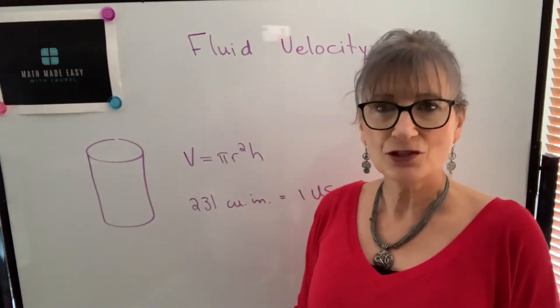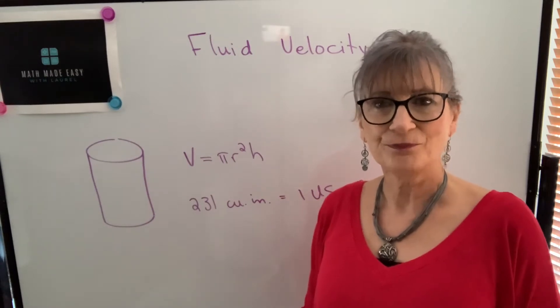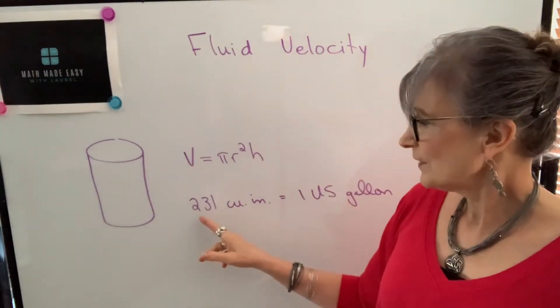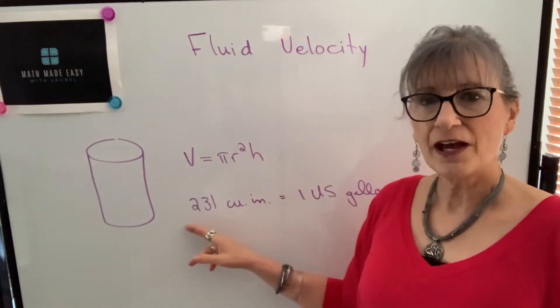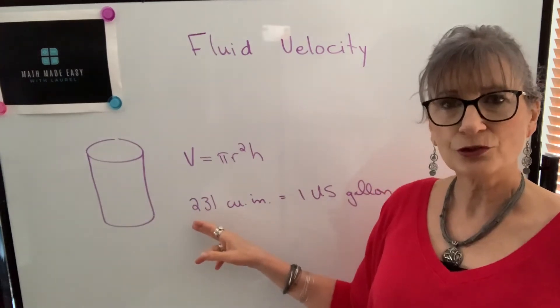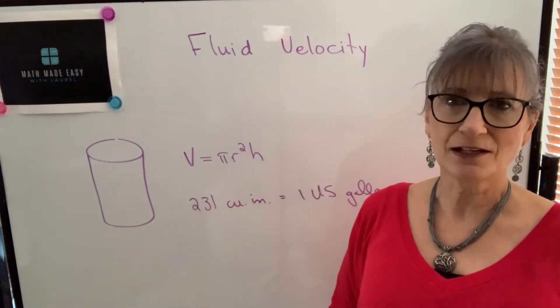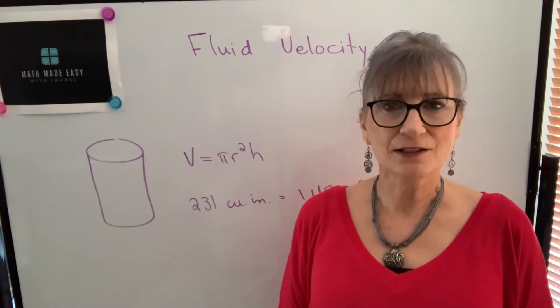And that, if your dimensions are in inches, will give you volume in cubic inches. The other thing that we're going to use is the fact that there are approximately 231 cubic inches in a U.S. gallon. When we're working with pump capacity, it will be expressed in gallons per minute, and that means American gallons per minute.